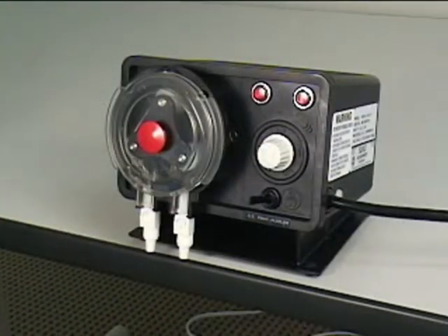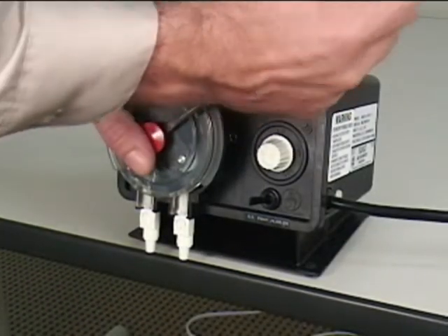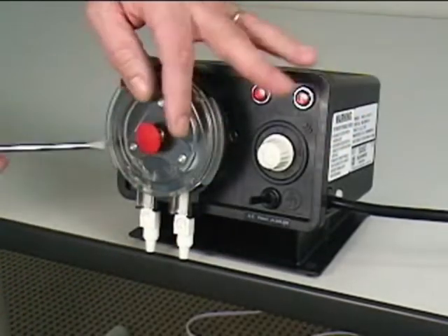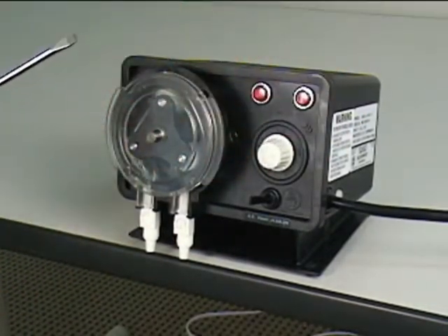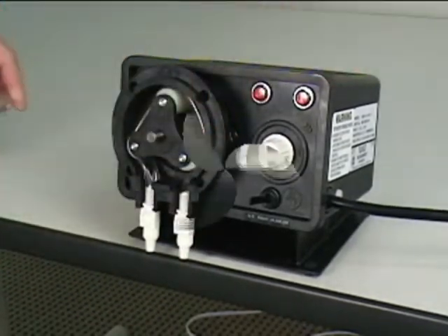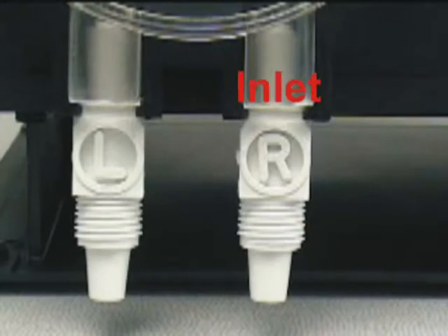Using a screwdriver, gently pry off the cover's retaining knob. Remove the cover by pulling on the tabs located on the sides of the cover. The right side of the pump tube is marked with the letter R. This is the inlet side of the pump tube. The left side of the pump tube is marked with the letter L. This is the outlet side of the pump tube.